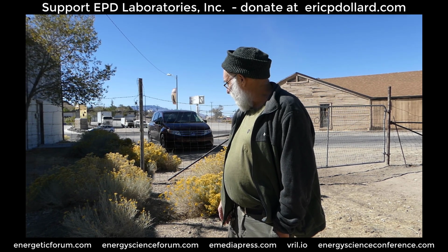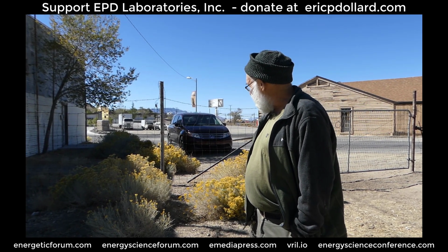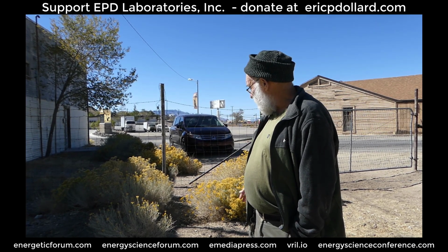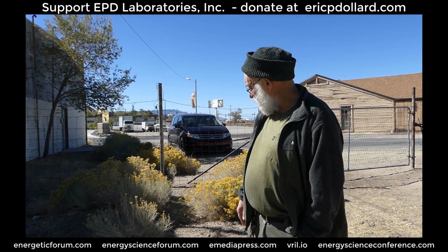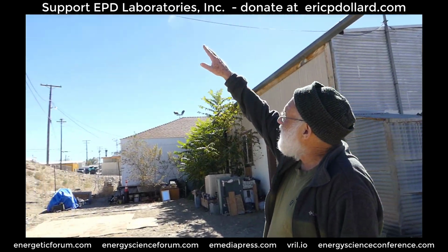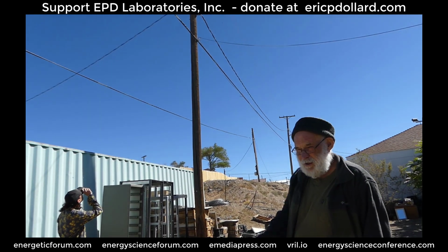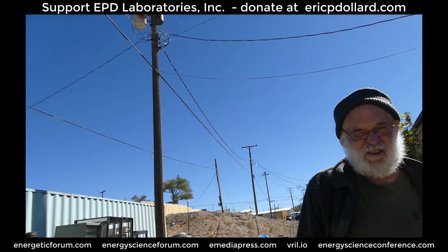So the only way to deal with that is to put in a wooden pole away from the building and terminate the electrical service on that, and the meter and everything goes on that, and then plastic pipe will carry it into the transformers into the building to keep any of the MV energy neutral transients out of the building. Now, the only way that the power company will cooperate in alleviating this mess up here is to put in another pole, and they will not provide a delta connection. That's not totally their fault. The National Electrical Code people that have got their fingers in regulating that are working hard to eliminate the delta, but they will give us a delta primary, and also they have agreed tentatively to not connect the high voltage neutral to our neutral.